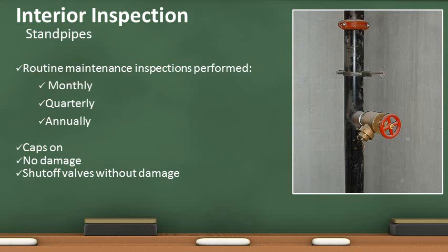Interior standpipes have the same requirements as exterior standpipes. There should be no debris inside the inlets, and caps must be securely affixed. Again, nothing is to be attached to any component of this system. Documentation of monthly, quarterly, annual, and 5-year inspection, testing, and maintenance is required.